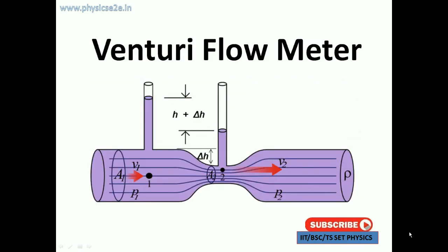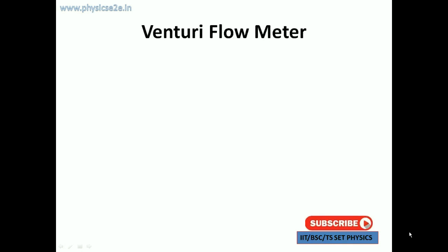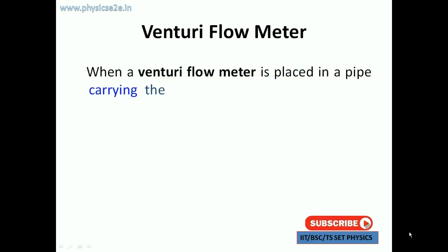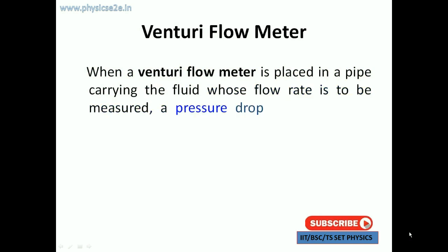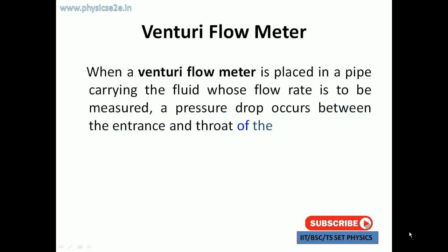Venturi flow meter part 2. The Venturi flow meter is a mechanical type flow meter and it is a variable pressure type flow meter. When a Venturi flow meter is placed in a pipe carrying the fluid whose flow rate is to be measured, a pressure drop occurs between the entrance and throat of the Venturi flow meter. Similar to an ammeter placed in a circuit in series, the Venturi flow meter is also placed in series type in the pipeline.